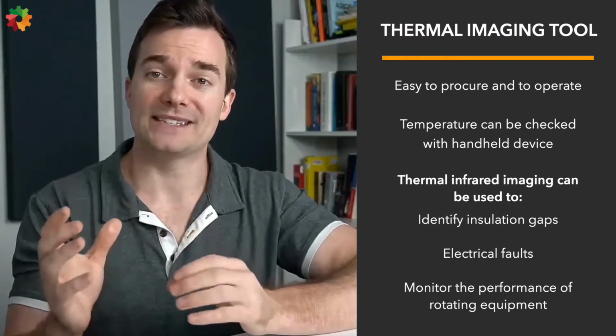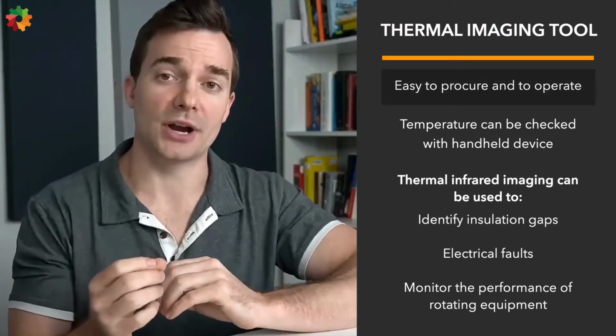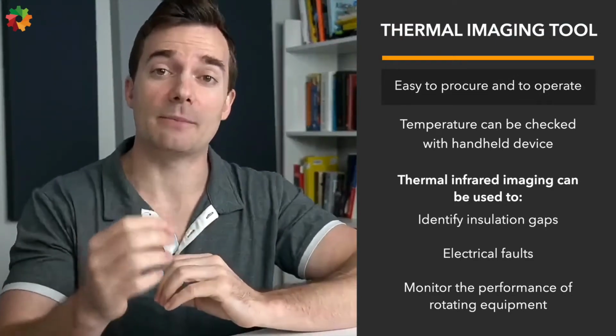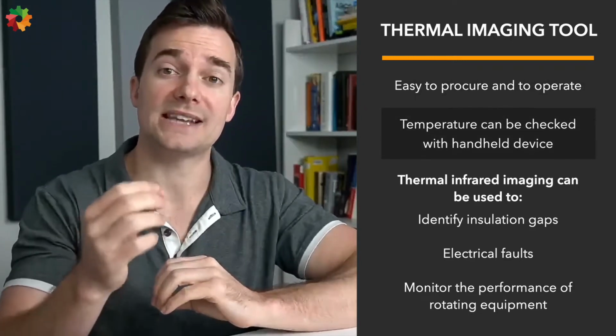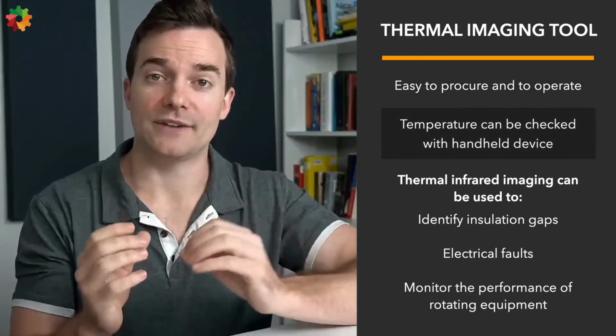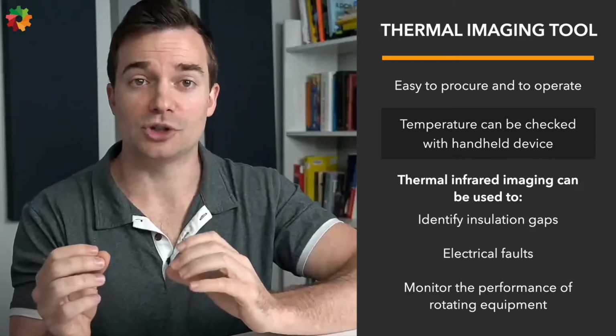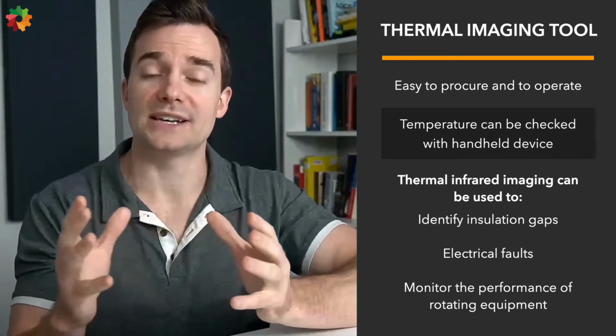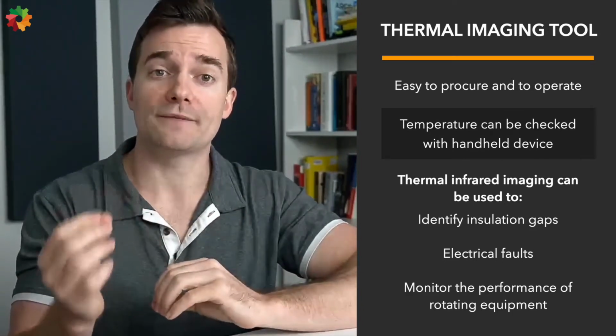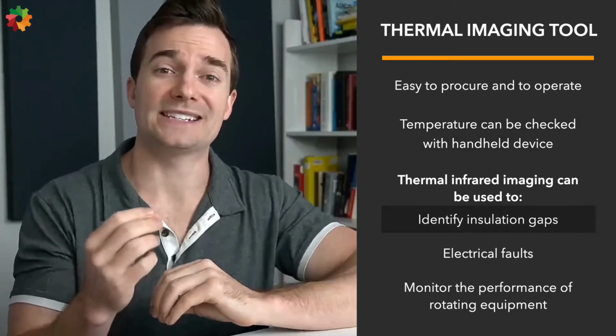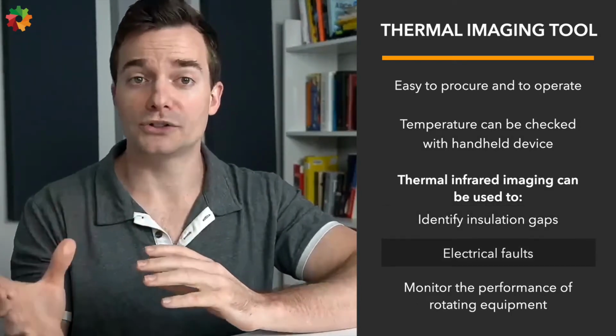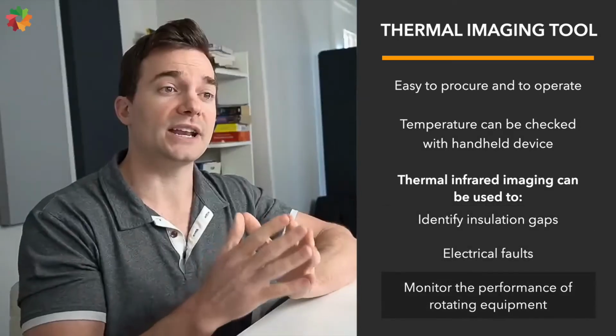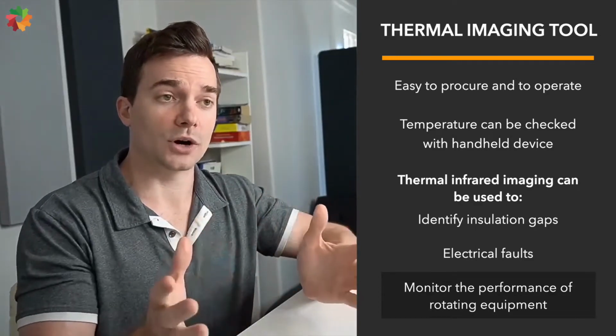This type of equipment is easy to procure and easy to operate. In its simplest form, plant operators and technicians can obtain temperature readings with a handheld device, avoiding equipment downtime due to a planned shutdown for a routine inspection. With thermal infrared imaging, you can quickly identify insulation gaps, electrical faults, and monitor the performance of rotating equipment on your plant floor. Now let's go ahead and take a look at an image of the device in the next part of this video.